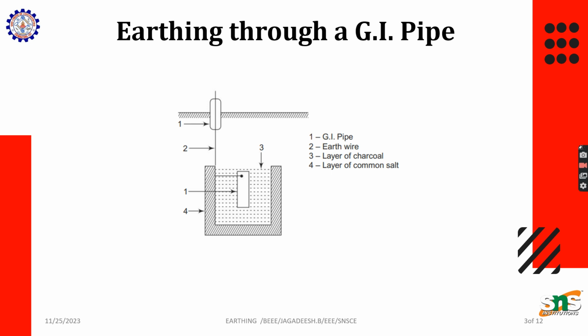The charcoal and salt used here increase the conductivity, so that when a human body touches the machine, the leakage current should not flow through the human body, because the human body also has a resistance. So the charcoal and salt will reduce the resistance, so that the leakage current does not pass to the human body, and the leakage will flow through the earth point. So that is the process.